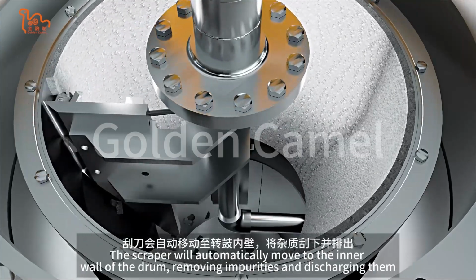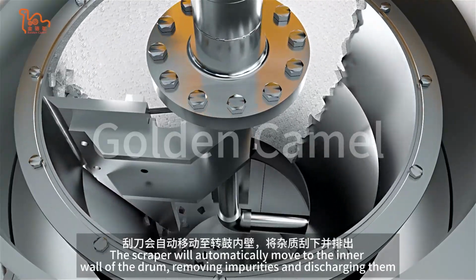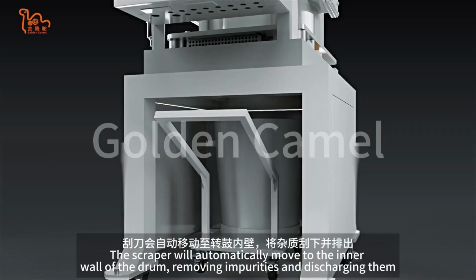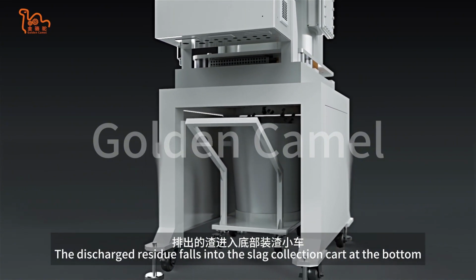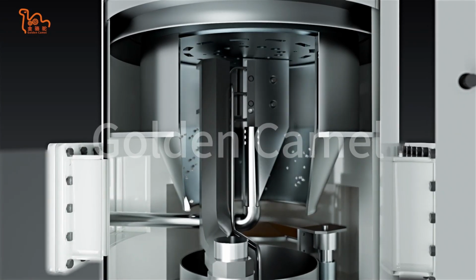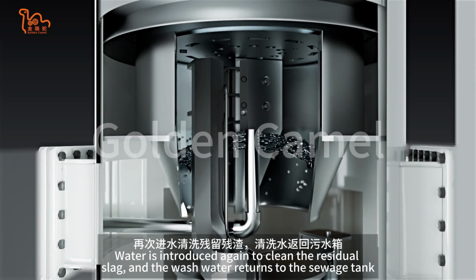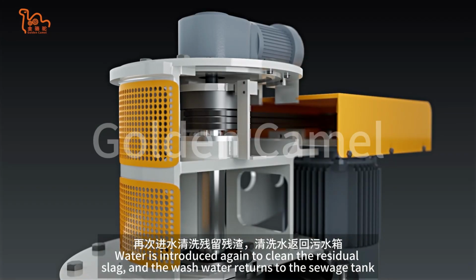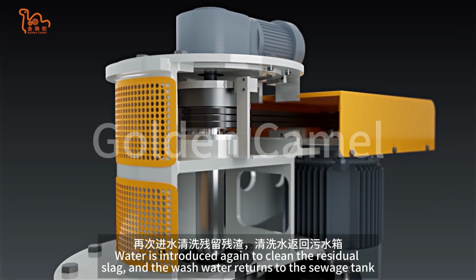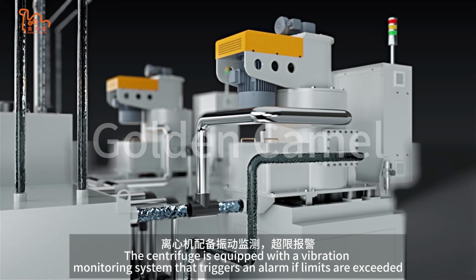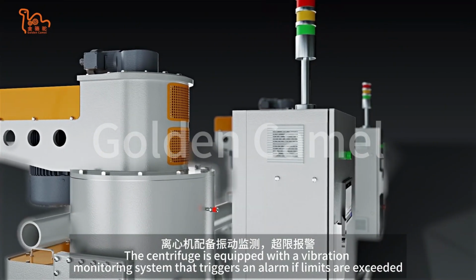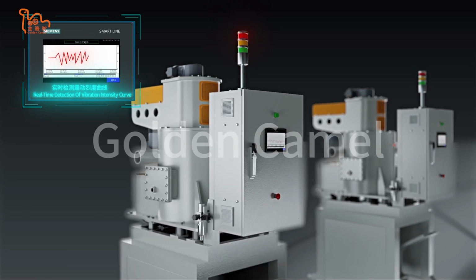The scraper will automatically move to the inner wall of the drum, removing impurities and discharging them. The discharged residue falls into the slag collection cart at the bottom. Water is introduced again to clean the residual slag, and the wash water returns to the sewage tank. The centrifuge is equipped with a vibration monitoring system that triggers an alarm if limits are exceeded.